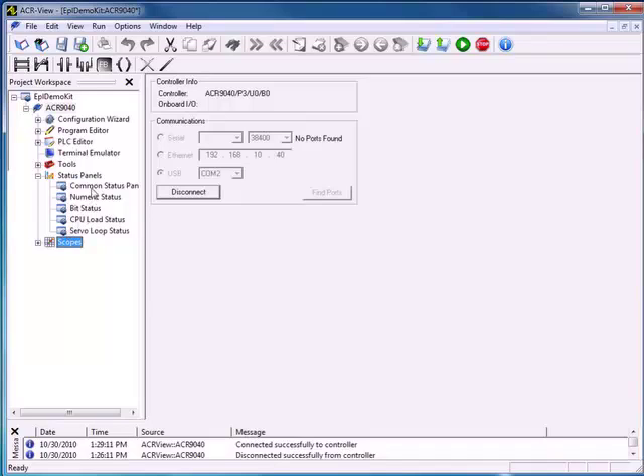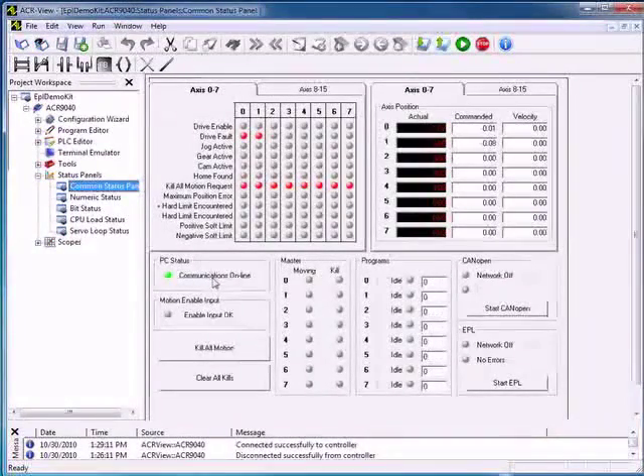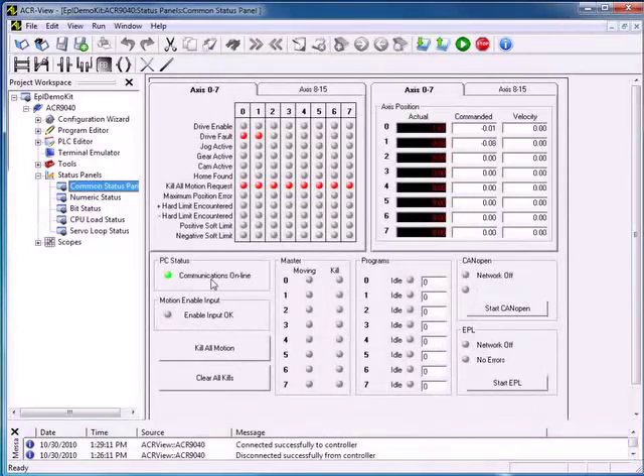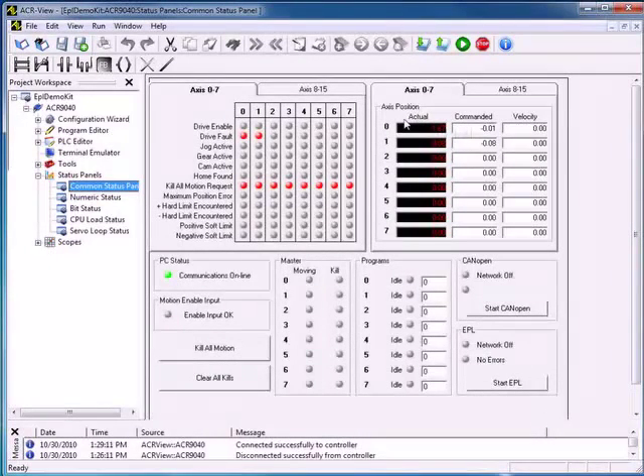Let's begin with the common status panel. We can see that I am communicating with the PC. Currently my CAN open and EPL networks are off. My drives are faulted and I have a kill all motion request. We can determine our actual, commanded, and velocity for each axis. Our motion enable is powered, giving us an enable input OK. If we did not have power to our enable input, we would see the fault here.